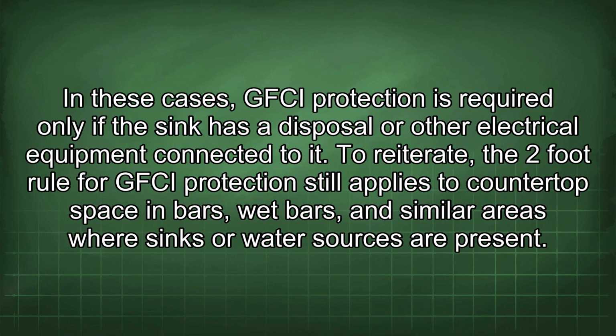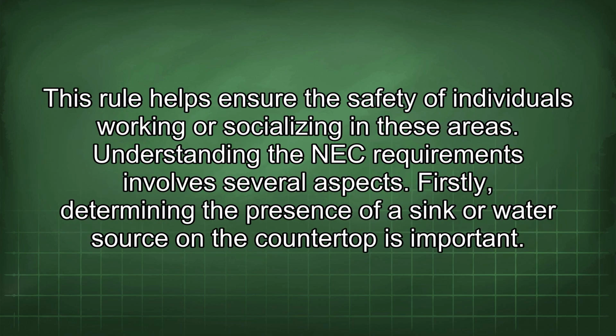In these cases, GFCI protection is required only if the sink has a disposal or other electrical equipment connected to it. To reiterate, the 2-foot rule for GFCI protection still applies to countertop space in bars, wet bars, and similar areas where sinks or water sources are present. This rule helps ensure the safety of individuals working or socializing in these areas.